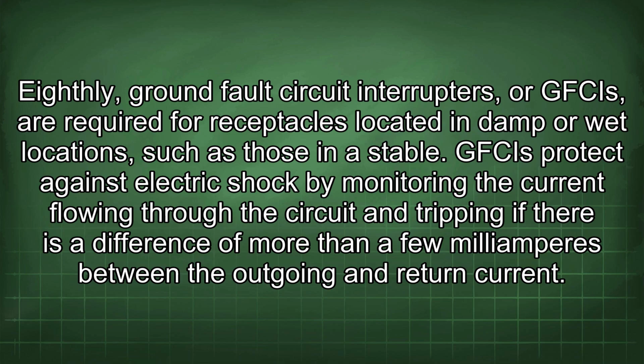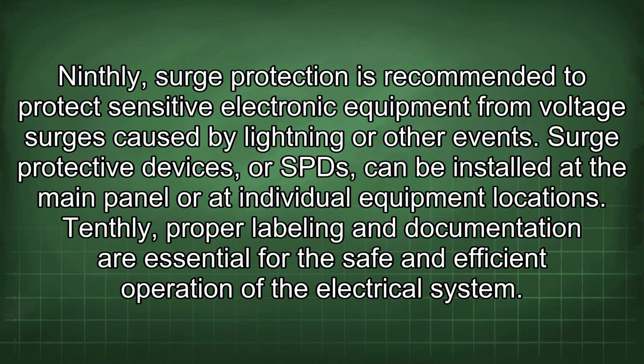GFCIs protect against electric shock by monitoring the current flowing through the circuit and tripping if there is a difference of more than a few milliamperes between the outgoing and return currents. Ninthly, surge protection is recommended to protect sensitive electronic equipment from voltage surges caused by lightning or other events. Surge protective devices, or SPDs, can be installed at the main panel or at individual equipment locations.